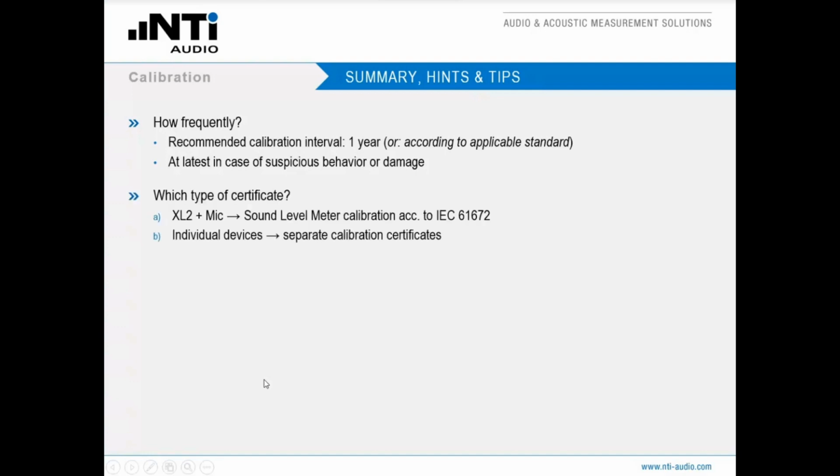Which type of certificate do you need? If you send us the XL2 plus microphone, we recommend the sound level meter calibration according to the IEC 61672. Otherwise, if you send us an individual device, an MR Pro, an FX100, whatever, we will do the separate calibration, the individual calibration.